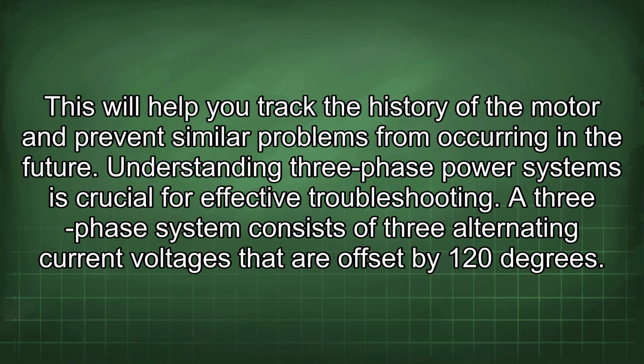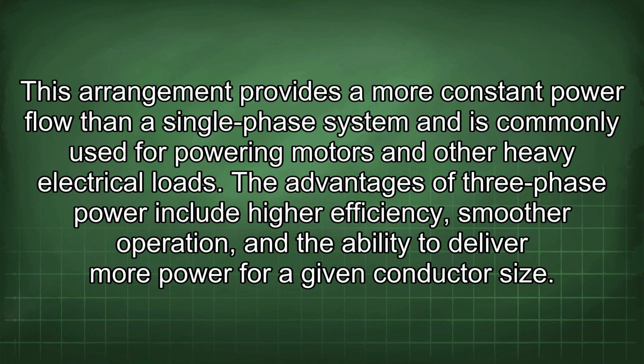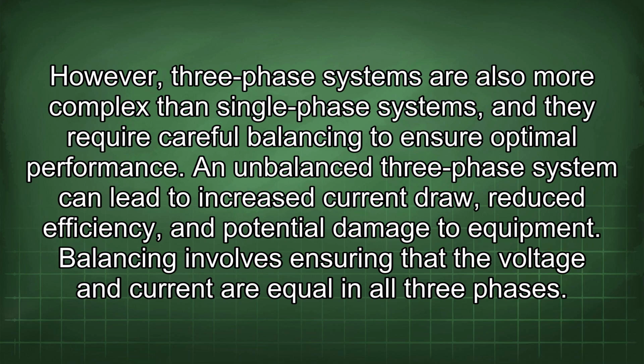Understanding three-phase power systems is crucial for effective troubleshooting. A three-phase system consists of three alternating current voltages that are offset by 120 degrees. This arrangement provides a more constant power flow than a single-phase system and is commonly used for powering motors and other heavy electrical loads. The advantages of three-phase power include higher efficiency, smoother operation, and the ability to deliver more power for a given conductor size. However, three-phase systems are also more complex than single-phase systems, and they require careful balancing to ensure optimal performance.